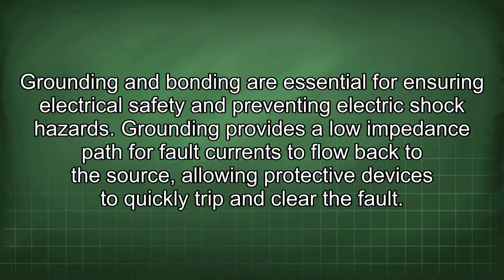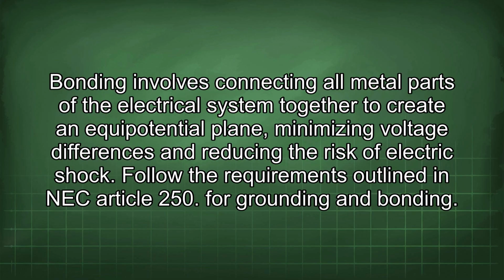Grounding and bonding are essential for ensuring electrical safety and preventing electric shock hazards. Grounding provides a low impedance path for fault currents to flow back to the source, allowing protective devices to quickly trip and clear the fault. Bonding involves connecting all metal parts of the electrical system together to create an equipotential plane, minimizing voltage differences and reducing the risk of electric shock.